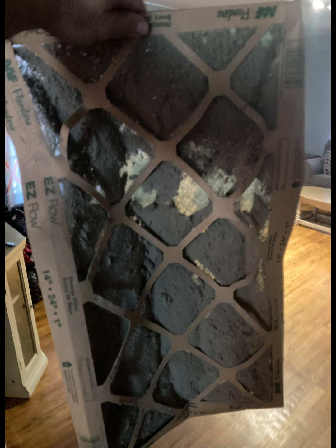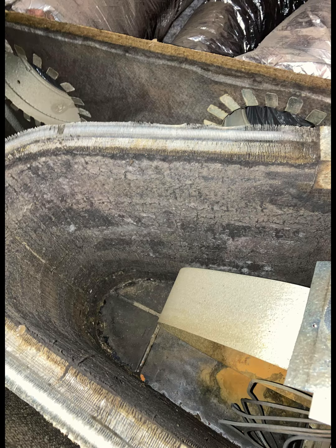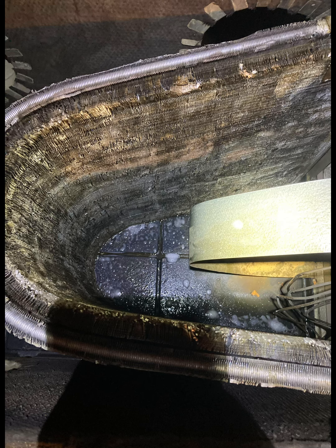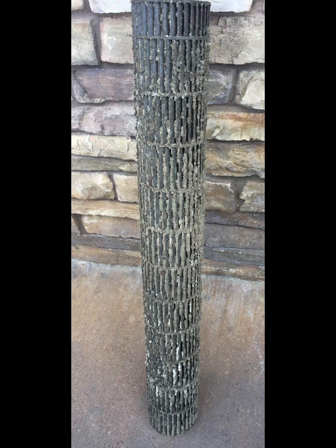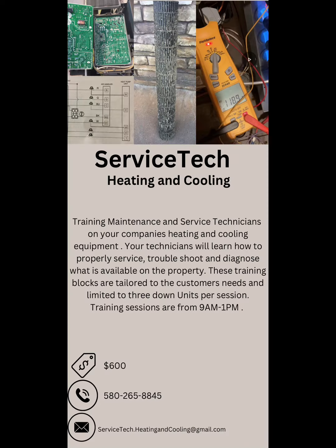Oh yes, dirty coils that are so caked up from years of neglect, from not being on a PM service of any nature, and it's just not allowing that air to pass. The same as dirty motors. I'm going ahead of myself. Just dirty in general really causes the number 1 cause of problems that I see. I should have put it as number 1 instead of the flame sensor.